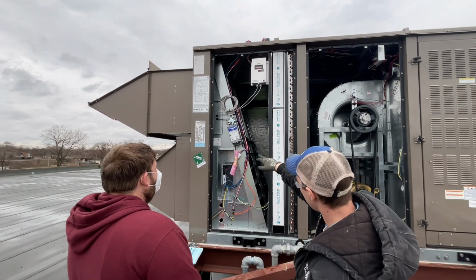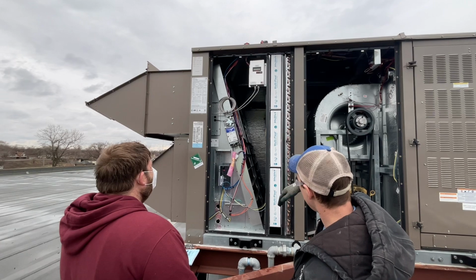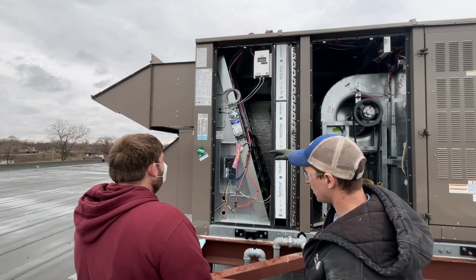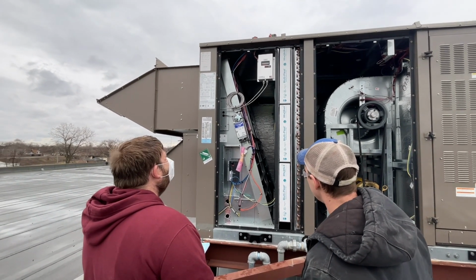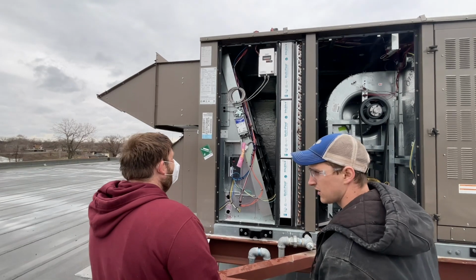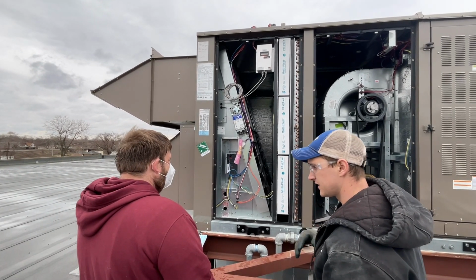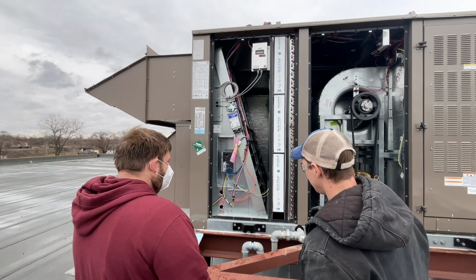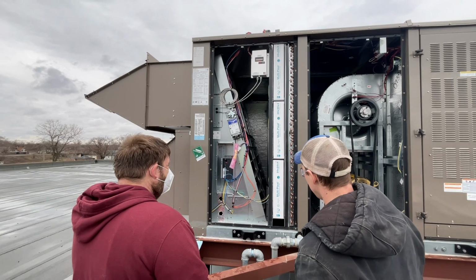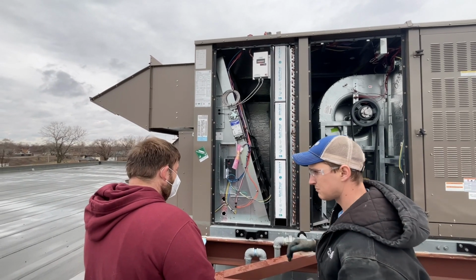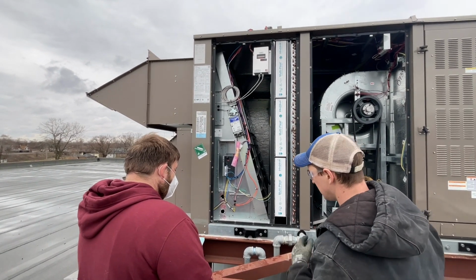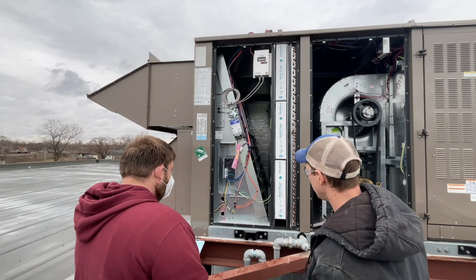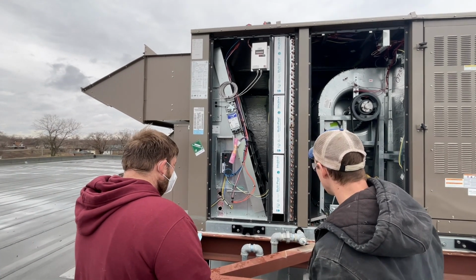I've got an actuator for the economizer, which will change from return air to outside air. It does have automatic. There's no need to change anything in the controls. It's all based on enthalpy. If it sees that it's better to take outside air, or what the unit needs to do, it'll do that. Don't really adjust for the filters.